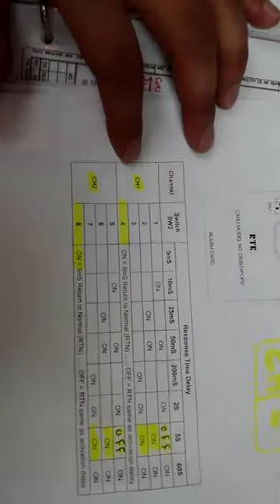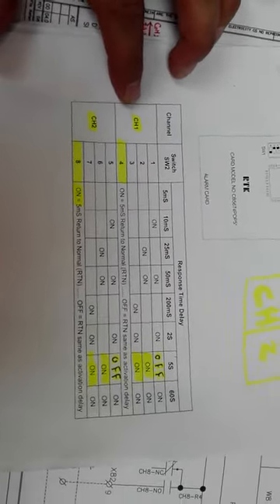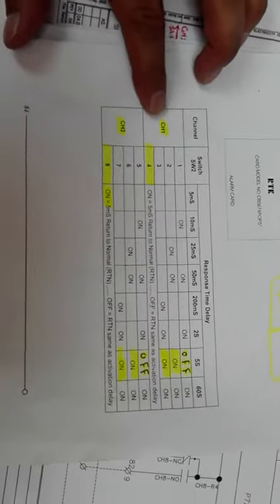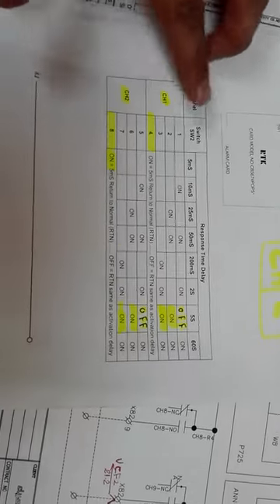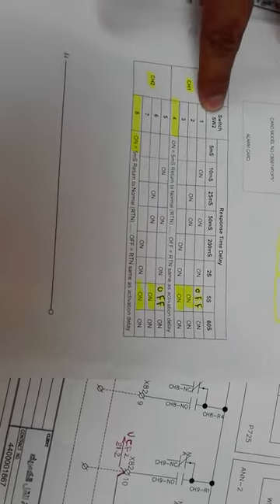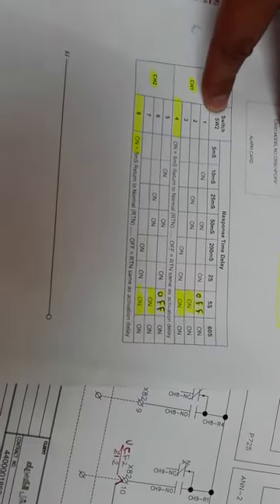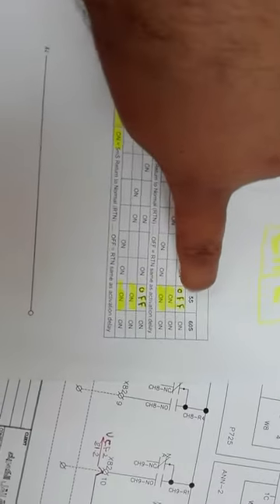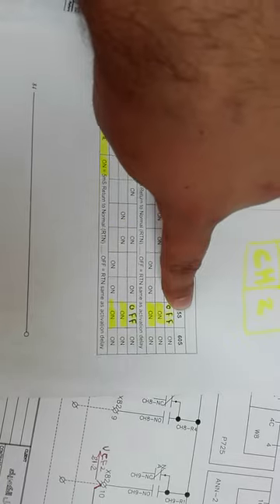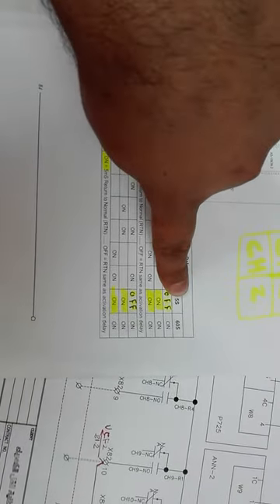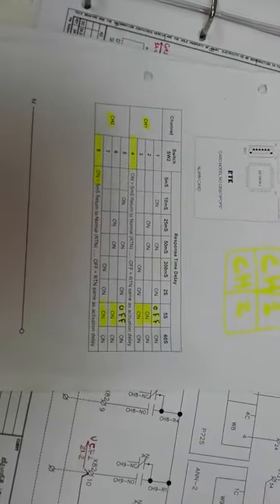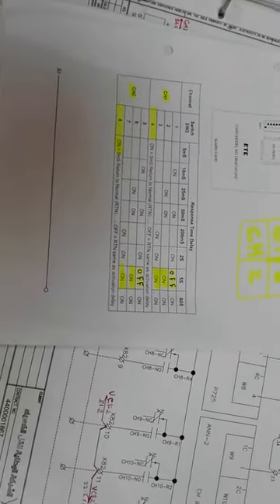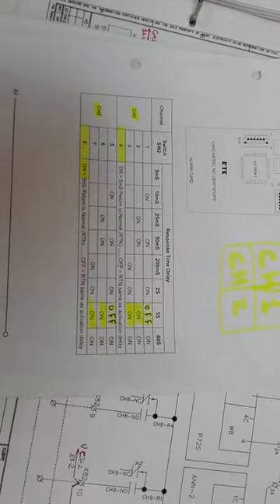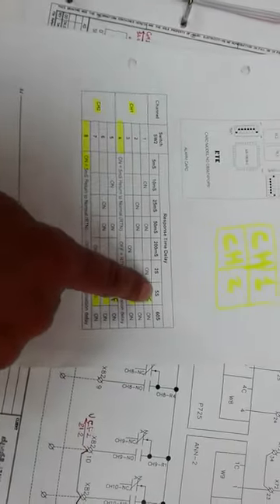So per our settings, as I discussed before by showing you the cards for channel 1 and channel 2, we changed the settings for switch SW2. The settings we made are for 5 seconds. Now we will check whether it is working according to the settings we made. For that we will measure the time delay. We need a timer to measure the time between start and stop. Is it coming to 5 seconds or not?